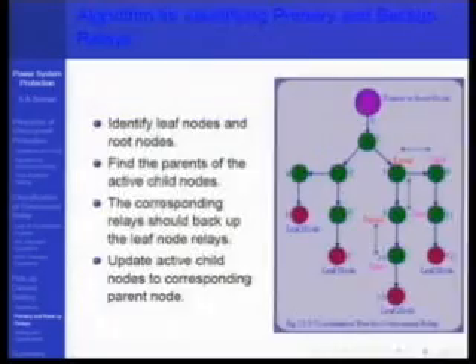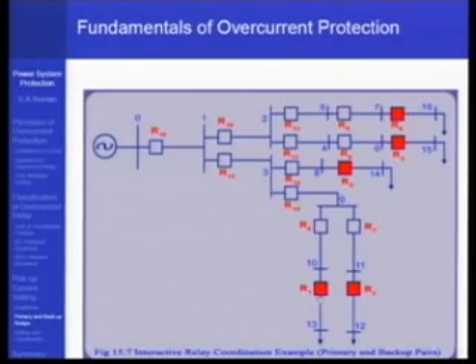So in this system, for example, these are the relays which you will set first: R1, R2, R3, R4, R5. They have only primary protection responsibility. They don't have any backup responsibility. Then you go and set the relays which are backing them up. So these are the red relays which are backing them up. These are the next set of relays which you set up. Then the backup relays become the primary relays in some sense, and then the next relays are to be set up.